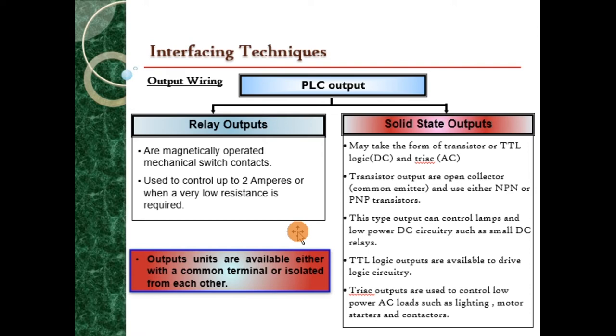The PLC can be connected to outputs by using a relay or solid-state output. A relay is a magnetically operated mechanical switch contact, and it can be used to control up to 2 amperes, or when very low resistance devices are required. While the solid-state outputs can take the form of TTL, which is transistor-transistor logic, or triac. The transistor outputs are often open collector, using a common emitter, and use either an NPN or PNP transistor. This type of output can control lamps and low power DC circuits, such as small DC relays. The TTL logic outputs are available to drive logic circuitry, either 1 or 0, or 0 or 5 volt. While the triac outputs are used to control low power AC loads such as lighting, motor starters and contactors.